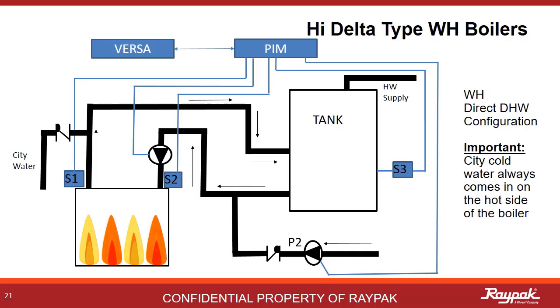Moving on from hydronic and into WH-type appliances, as in water heaters. When a high-delta is purchased to be a water heater, there is only one mode of operation, so the plumbing is more specific. City cold water always comes in on the outlet side of the boiler to be mixed with the hot water the boiler is producing on the way to the tank. Introducing city cold water on the inlet side of the boiler will likely lead to going below the required minimum inlet temperature of 105 degrees Fahrenheit, resulting in condensing in the boiler. Here the tank works like a decoupler, and the S3 system sensor is placed in a dry well in the tank.